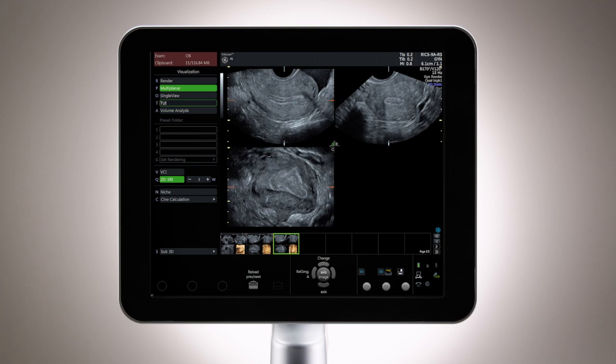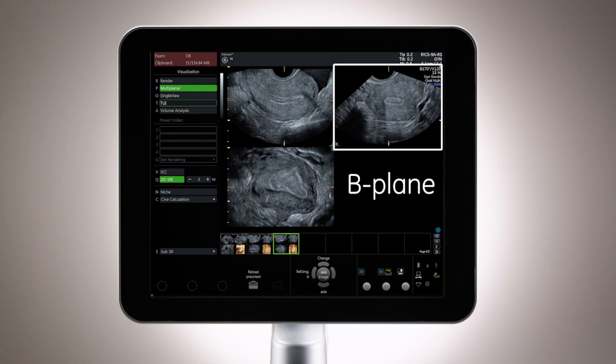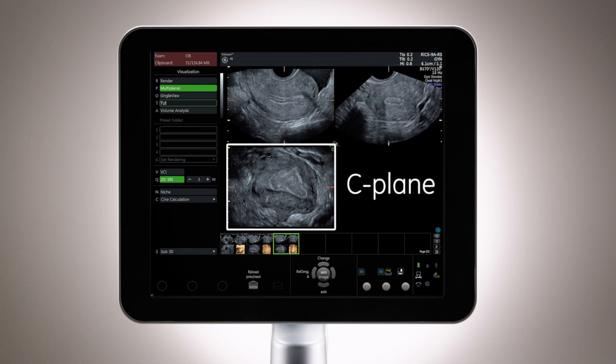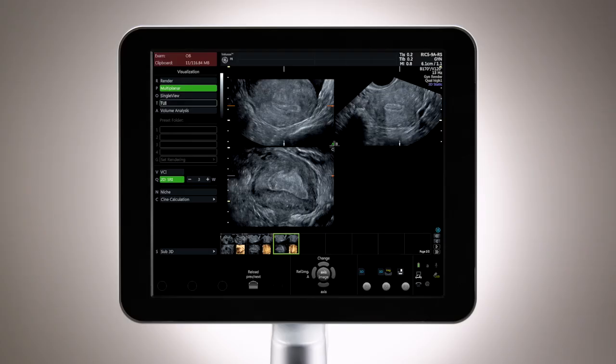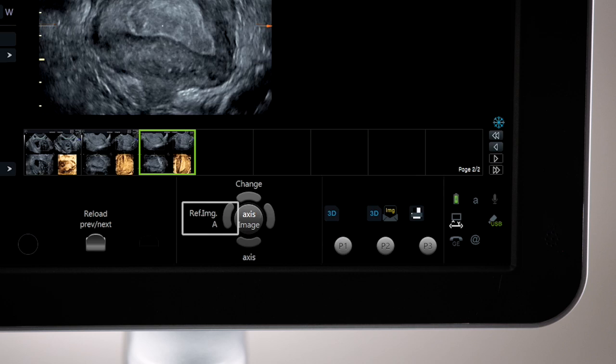In this quad display, the upper left image is known as the A plane, the plane of acquisition. The upper right image is known as the B plane, which is 90 degrees orthogonal cross-section from the A plane. The lower left image is known as the C plane, which is 90 degrees orthogonal in the horizontal direction of the A plane. The parallel shift control knob will pan through each of these planes to evaluate the anatomy in more detail. Select the reference image by using the trackball keys.